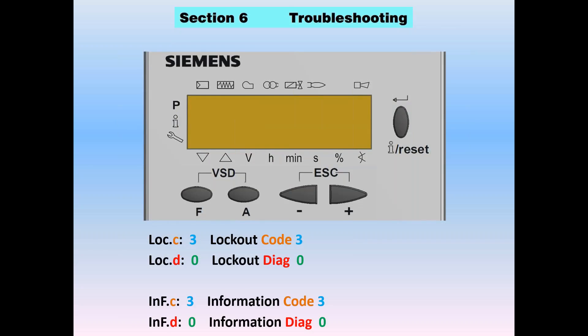When you get a fault on an LMV3, the screen is going to flash between LOCC and LOCD — basically telling us the lockout code (in this case it was 3) and a lockout diagnostic, detail 0. Sometimes the LMV doesn't lock out; it simply gives a fault with an information screen, displaying INFC and INFD for information versus a lockout, which is a shutdown.